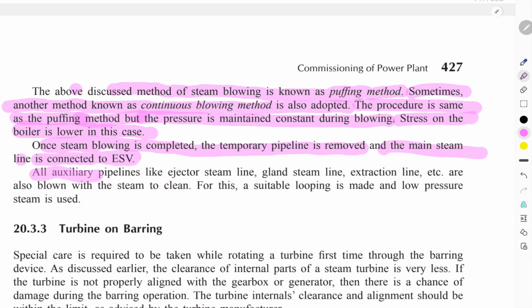Okay. All auxiliary pipelines, such as the ejector steam line, the gland steam line, and the extraction line, are also blown to clean the steam. For this, suitable looping is made and low pressure steam is used. Okay, low pressure steam. So this was the lecture.